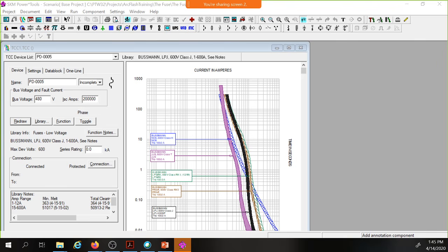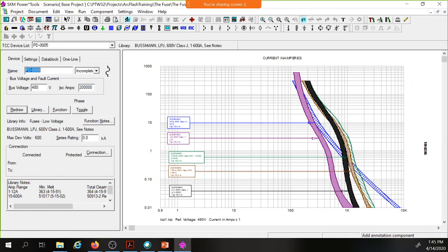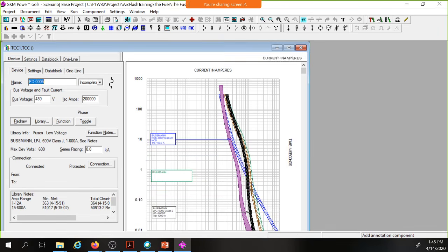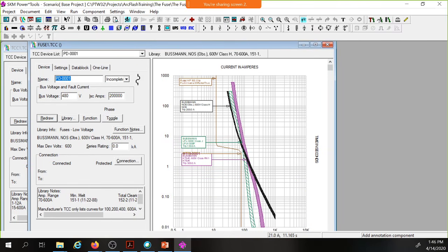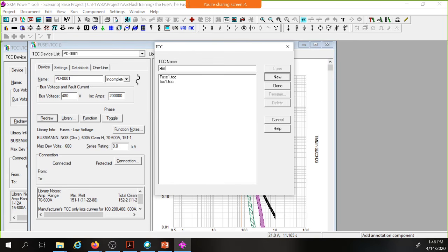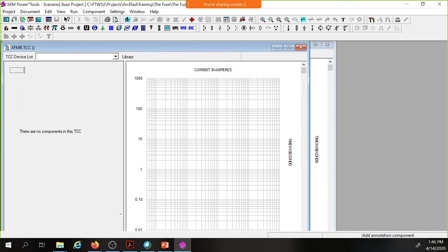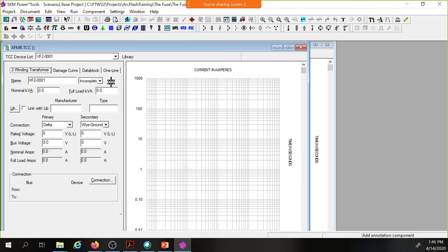All right, so I'm getting SKM up and running. Oh, there's SKM. I was working on this today. There are those fuses. Let's take a look, and this is my TCC1. This was my motor starting. Basically what we'll do is create a new one, call it XFMR, and add a transformer in. We'll say it's a 1500 kVA transformer, with 4160 primary and 480 secondary.